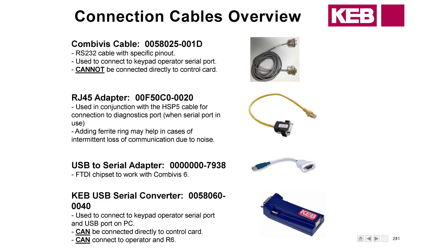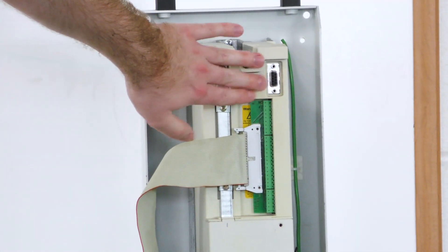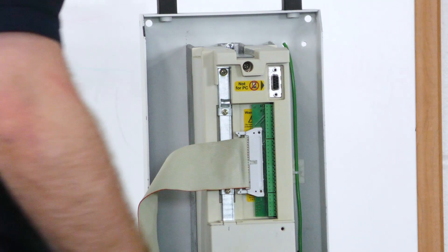To start out, we have a Combivis cable here — it's an RS-232 cable, but it has a different pinout. Unfortunately you can't go to Best Buy, buy an RS-232 cable, and use that. It has its own pinout. You cannot connect it to the control card. For example, on the R6, you can scope parameters where you would plug in right here, but you can't plug in the Combivis cable to this port here — you can damage the control card or your computer.